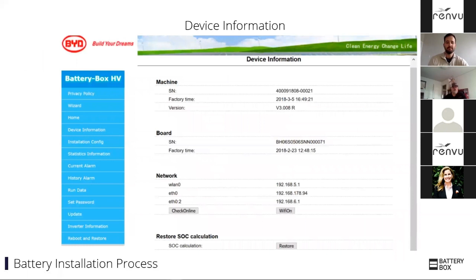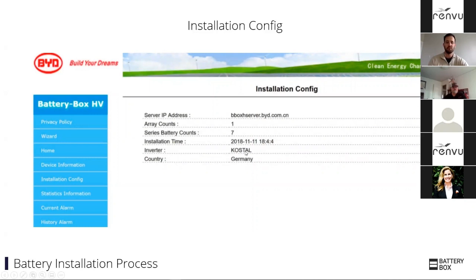You can also see that device information page, looking at the version and whatnot, and then the installation config page. This is where, once you've commissioned the battery, you want to make sure you did it right. You hop back in here and can see the settings you did. Okay, this is a stack with 7 modules. The inverter - this is from Germany, obviously - is a Kostal inverter. So you can verify that what you did was correct there.